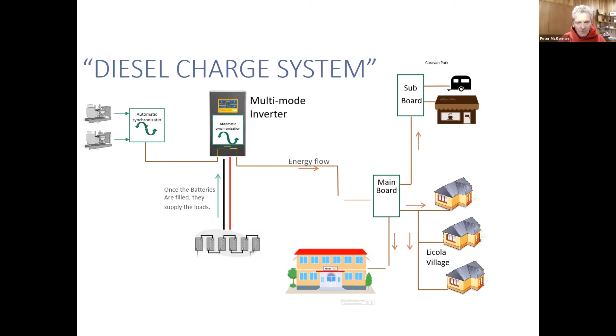The next thing you can do to a system like this is add what we call AC coupled solar. AC coupled solar looks a lot like the domestic systems you've seen about - it incorporates the same inverters you'd see on a domestic installation, and they synchronize with the grid. So either the grid is the actual output from the generators, or it's the output from the multi-mode inverter. Either way, there's a synchronous AC waveform, and the solar system joins in sync with that. Excess energy from the solar can be directed directly into the houses and caravan park, or converted to DC and stored in the batteries.